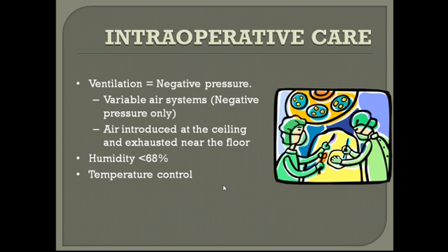The problem also is the technical difficulty of switching the AC from positive pressure to negative pressure. So it's advisable to hold drills, demonstrations and regular training for all healthcare professionals, speaking about biomedical staff and maintenance staff, on how to manage the HVAC system in order to accommodate such patients in the hospital service, especially since many unplanned surgeries, emergency or stat situations can involve TB cases, and they have to do it on the spot in the OR. So the maintenance personnel have to know how to switch off and how to reverse the pressure from positive to negative inside the theater during such airborne isolation procedures.